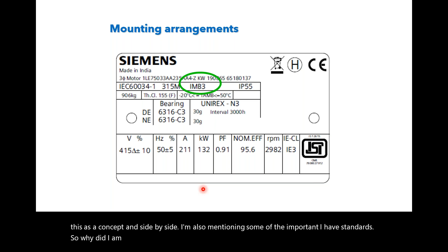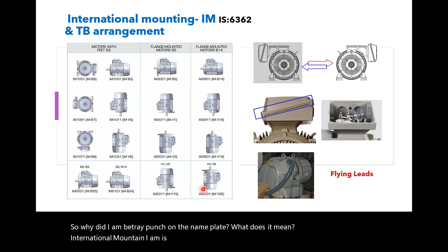Side by side, I'm also mentioning some important IS standards. So what is IMB3 punched on the nameplate? What does it mean? International mounting. IM is mounting. As you can see here, there are mounting samples shown. If there are feet, it's called IMB3. IMB6 is feet mounted on a wall with a shaft like this and the terminal box like this. This is horizontal foot mounting. The foot mounted arrangement can also be mounted like this. If it is B6 in this direction, B7 in this direction, V5 is foot but the shaft facing down. This is foot but the shaft facing up.